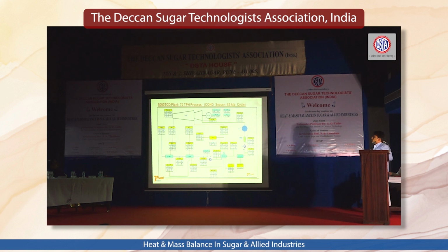Coming to a few case studies given by DSTA, we have simulated HMBD cases for 85 ata cycle, 105 ata cycle, and back pressure and condensing types. In this cycle, the turbine consists of 2 HP heaters, one deaerator, auxiliaries, and the condenser, with no LP heater. We have simulated this for 70 TPH of sugar steam at 2.5 ata.